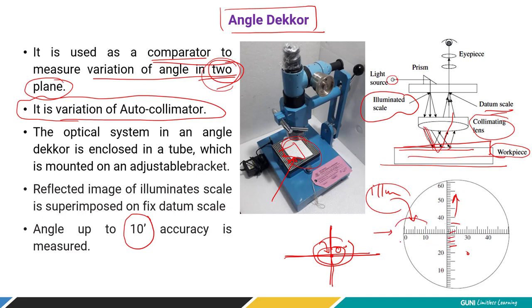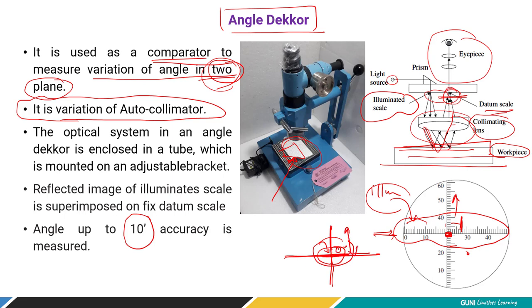The image of the illuminated scale is superimposed at 90 degrees due to reflection of the collimating lens over the datum scale. The point of intersection tells you the angle of tilt in both planes — the horizontal scale shows horizontal tilt and the vertical scale shows vertical tilt. The difference from the initial set position gives you the measurement: how much the surface is tilted horizontally and vertically.